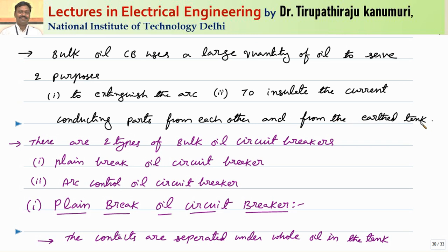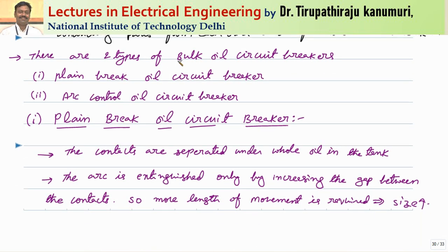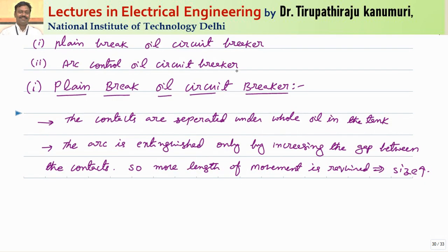The tank is generally made of iron and is earthed, so it provides insulation between the tank and the conducting parts as well as between the two live conductors at supply potential. For that purpose a huge quantity of oil is required. There are two types of bulk oil circuit breakers: the first invented is the plain break oil circuit breaker, and the second is the arc control oil circuit breaker, which was invented later and replaced the plain break type.